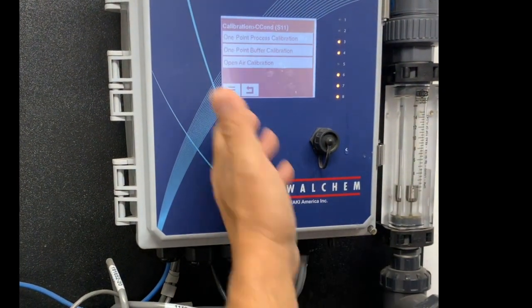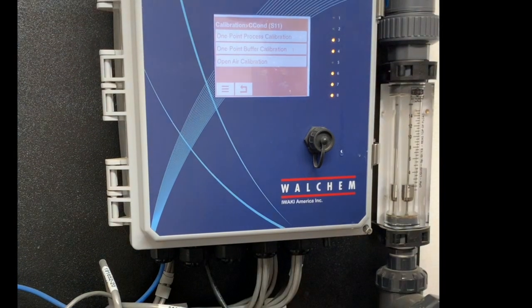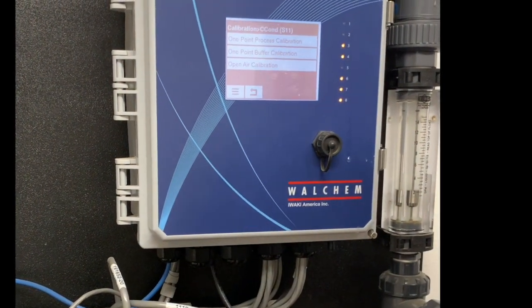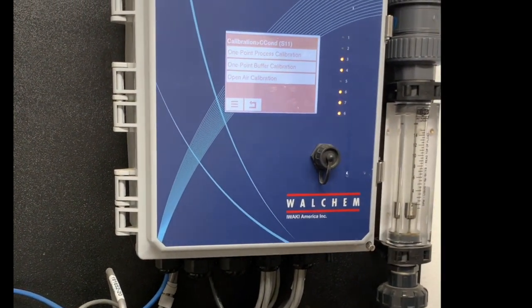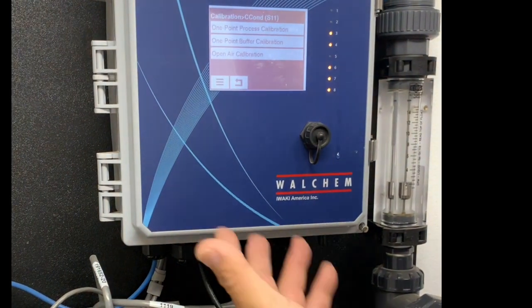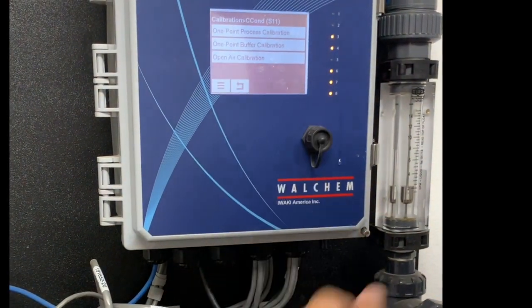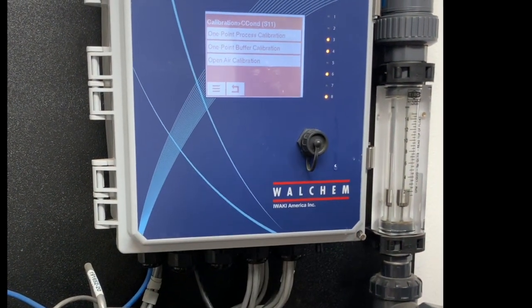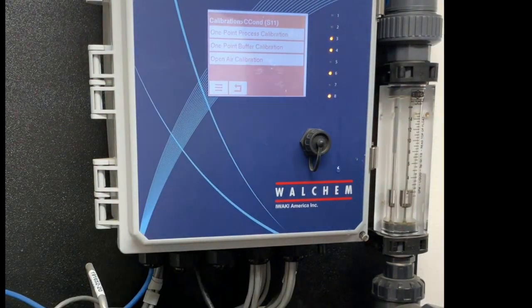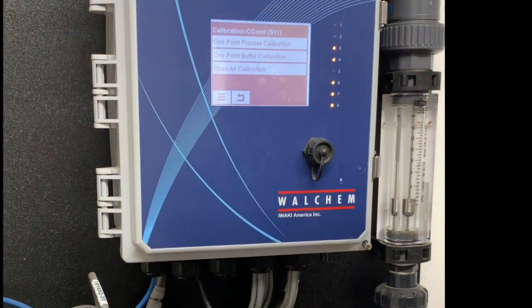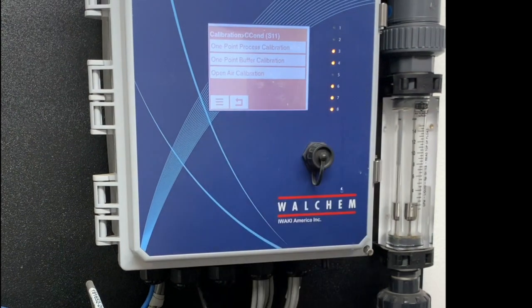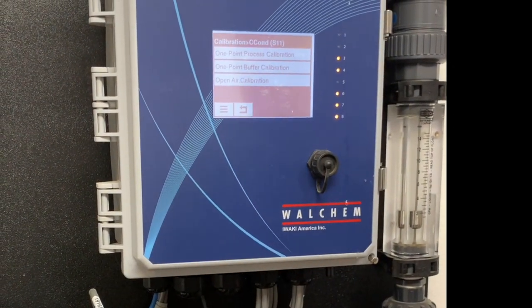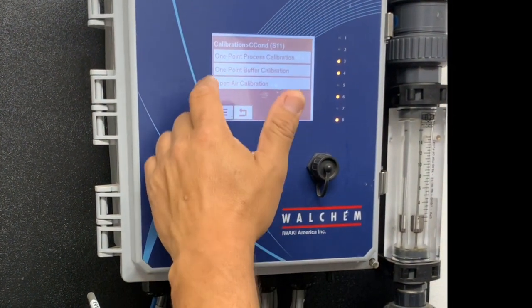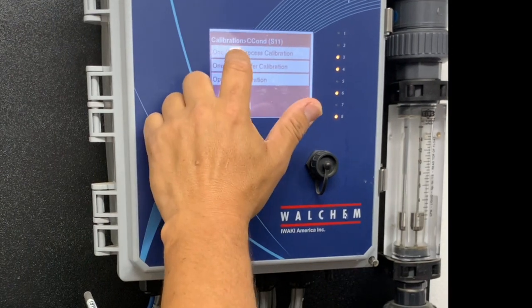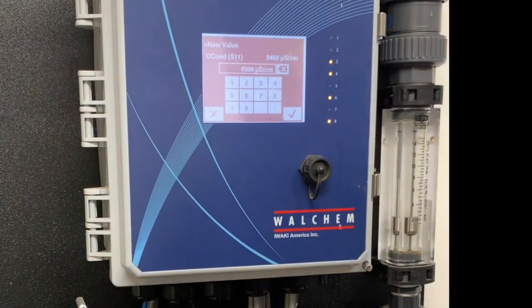And what that is basically reading is you're going to be reading air, which should be a 0 conductivity if there's no contaminants in the air. So you'll be reading a 0 calibration on that. You would actually pull the probe out, clean it, hold it to air, and it'll say 0. Or if it's off, then you would hit the calibration and put 0 in. In this process, we're going to do the 1-point process. So we'll hit the 1-point process.